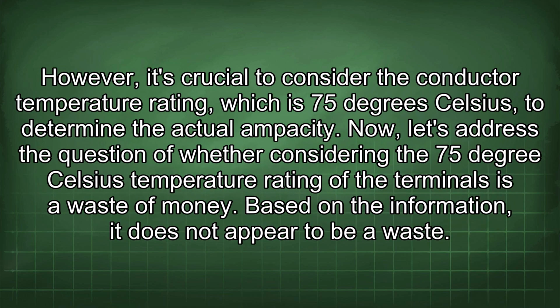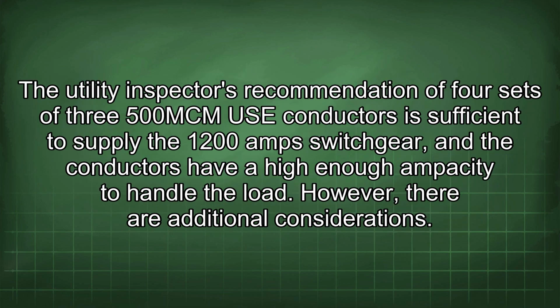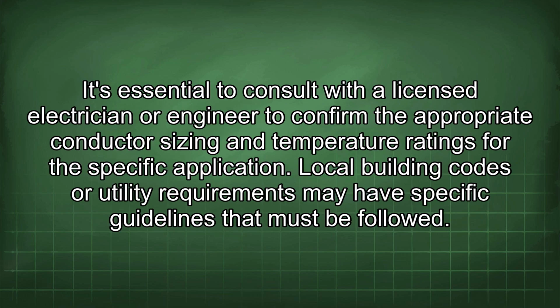However, it's crucial to consider the conductor temperature rating, which is 75°C, to determine the actual ampacity. Now, let's address the question of whether considering the 75°C temperature rating of the terminals is a waste of money. Based on the information, it does not appear to be a waste. The utility inspector's recommendation of 4 sets of three 500 mcm conductors is sufficient to supply the 1200 amps switchgear, and the conductors have a high enough ampacity to handle the load. However, there are additional considerations. It's essential to consult with a licensed electrician or engineer to confirm the appropriate conductor sizing and temperature ratings for the specific application. Local building codes or utility requirements may have specific guidelines that must be followed.